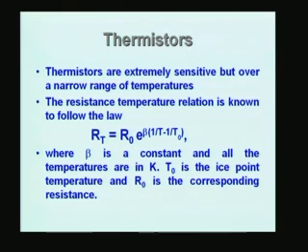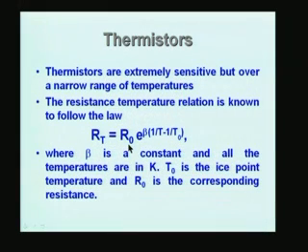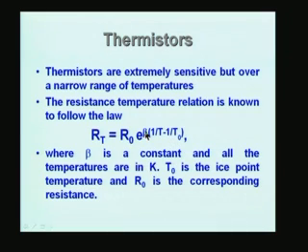Thermistors are extremely sensitive but over a narrow temperature range. The resistance-temperature relation follows: R_T = R0 × exp(β × (1/T − 1/T0)), where temperatures must be in absolute (Kelvin) scale, not Celsius. Beta is called the thermistor constant with units of Kelvin. T0 is the ice point temperature and R0 is the corresponding resistance.